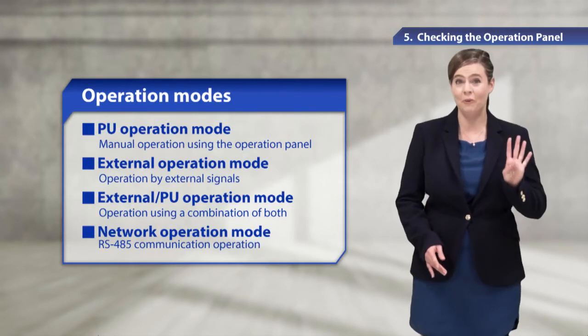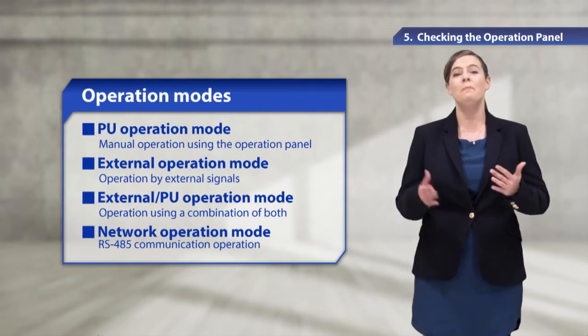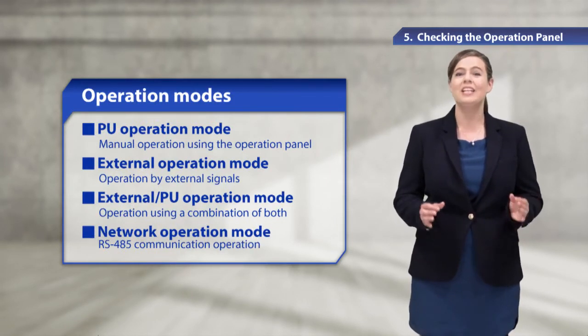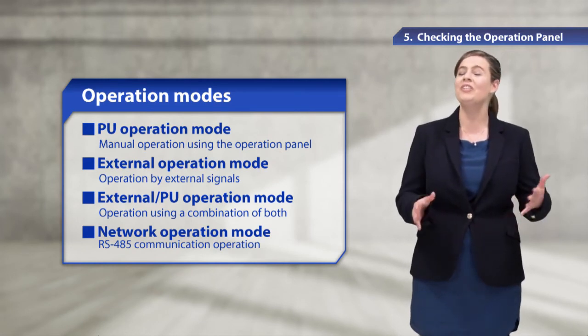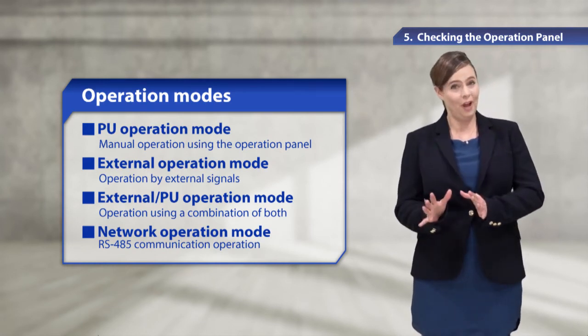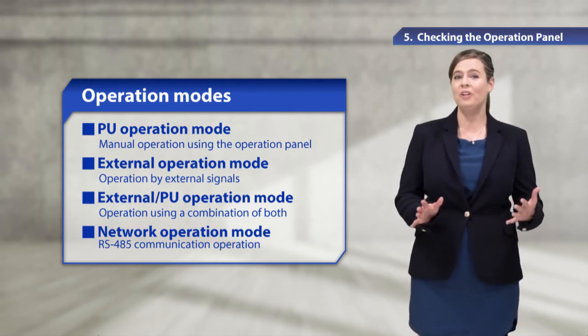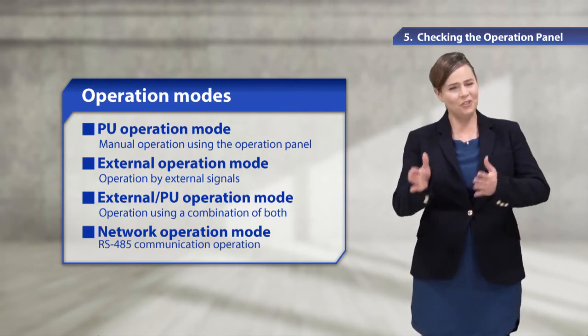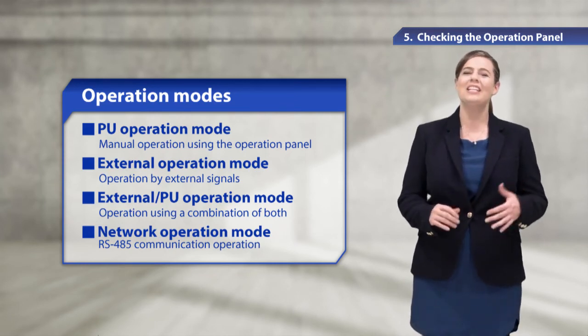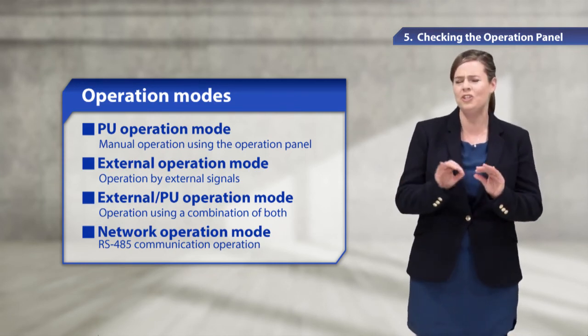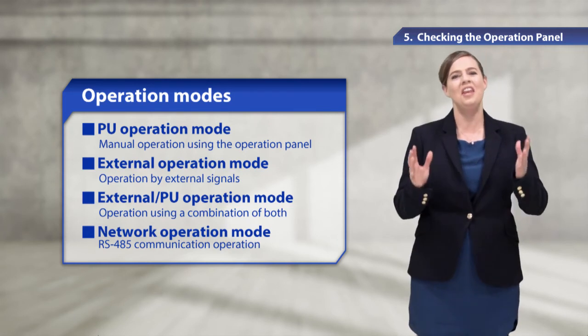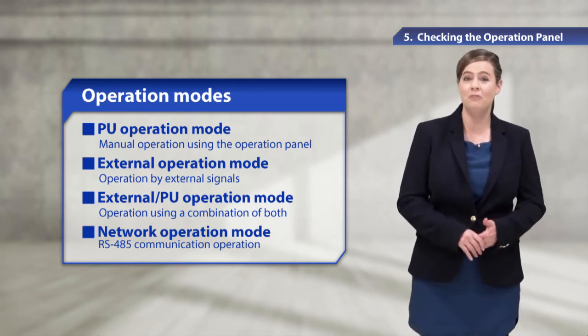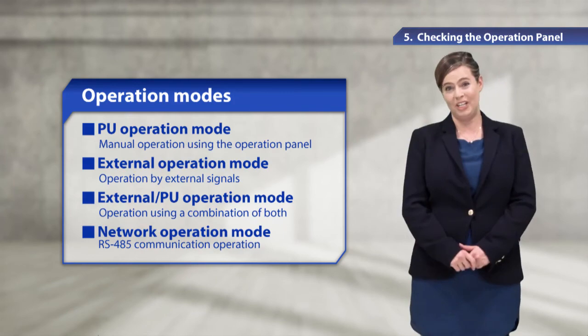I'll first introduce the operation modes. The inverter has four operation modes. The PU operation mode is for manual operation using the operation panel. The external operation mode is for operation by using external signals. The external PU operation mode is for operation using a combination of both. And the network operation mode is for the RS-485 communication operation.